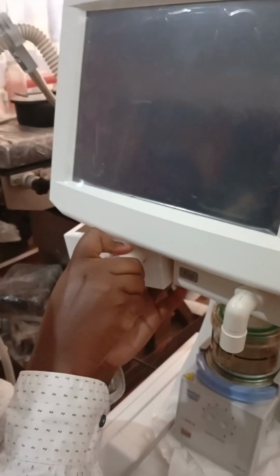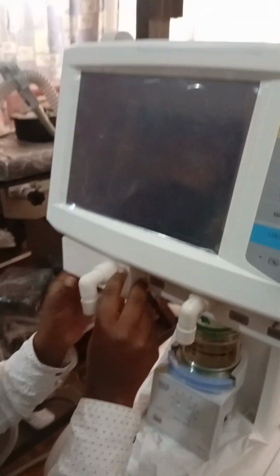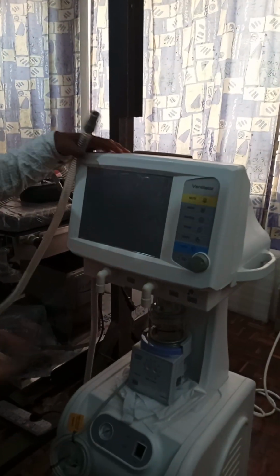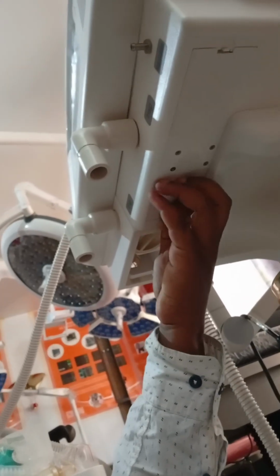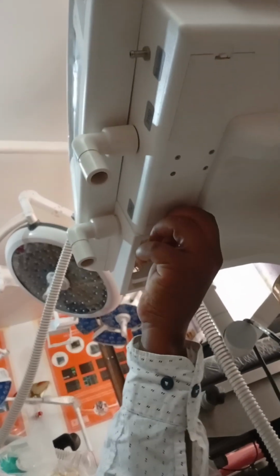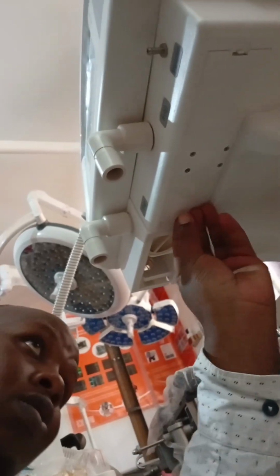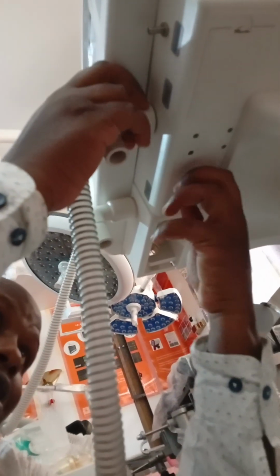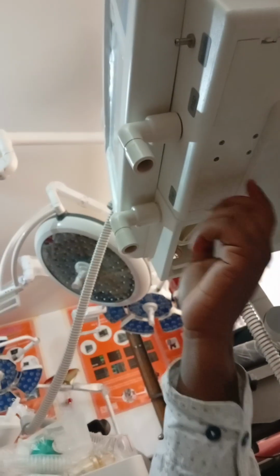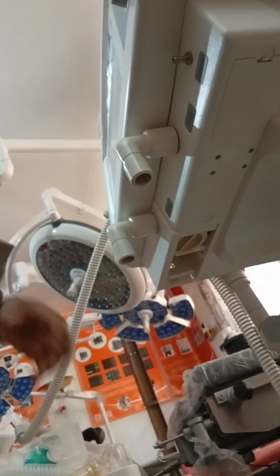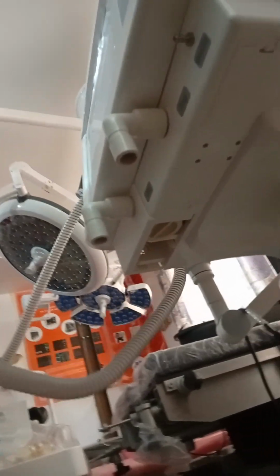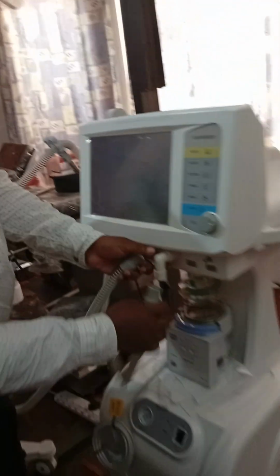So you need to be careful when fixing this one back. And then our machine also has an oxygen sensor. The oxygen sensor is usually at the bottom here. You need to open here. The oxygen sensor is down here. So for that one also, you change it after every 2 years.